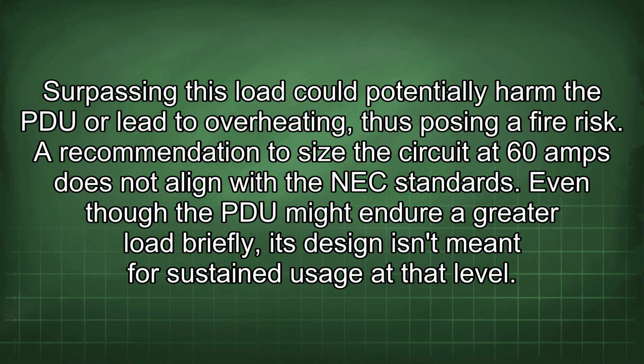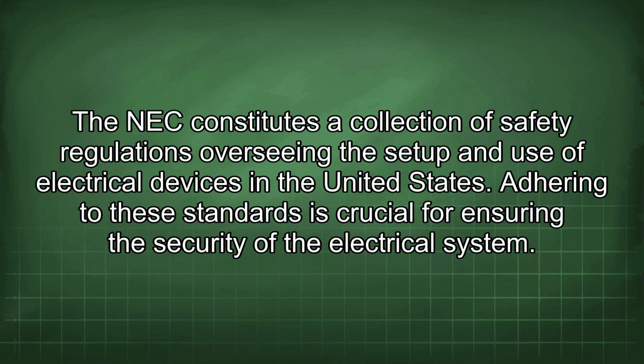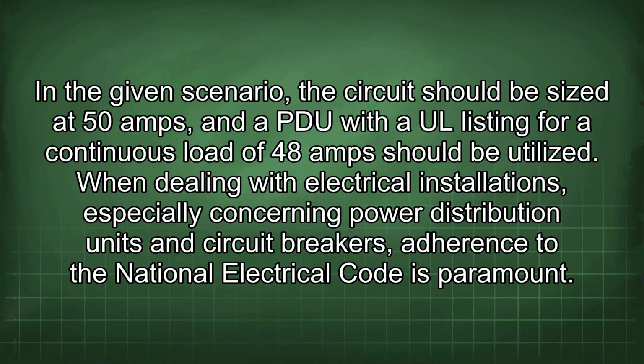A recommendation to size the circuit at 60 amps does not align with the NEC standards. Even though the PDU might endure a greater load briefly, its design isn't meant for sustained usage at that level. The NEC constitutes a collection of safety regulations overseeing the setup and use of electrical devices in the United States. Adhering to these standards is crucial for ensuring the security of the electrical system. In the given scenario, the circuit should be sized at 50 amps, and a PDU with a UL listing for a continuous load of 48 amps should be utilized.